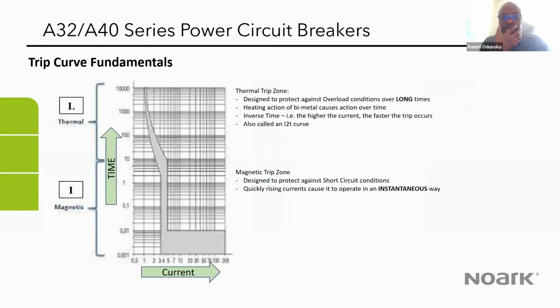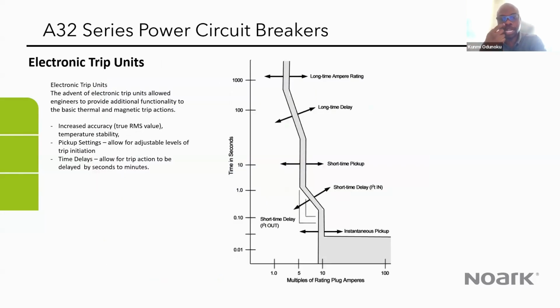But now we have the electronic trip units, which are like an advanced protection. One of the things the electronic trip unit does is that, instead of having the bimetallic trip and the solenoid, you would have a combination of semiconductor components: the diode, the thyristors, microprocessors. So it gives you more accuracy in terms of the RMS value that you're measuring. Also, there is better temperature stability with the electronic trip unit. And the protection settings are adjustable. You have a wider range of adjustment.